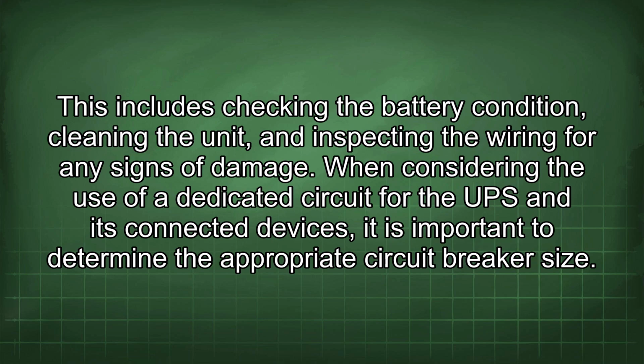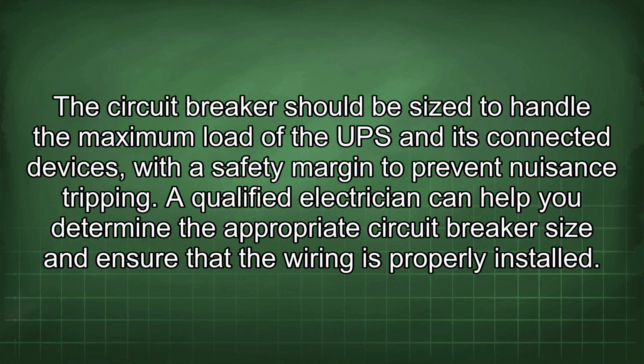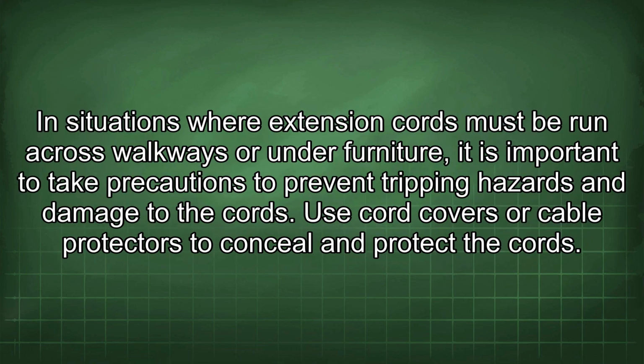When considering the use of a dedicated circuit for the UPS and its connected devices, it is important to determine the appropriate circuit breaker size. The circuit breaker should be sized to handle the maximum load of the UPS and its connected devices, with a safety margin to prevent nuisance tripping. A qualified electrician can help you determine the appropriate circuit breaker size and ensure that the wiring is properly installed. In situations where extension cords must be run across walkways or under furniture, it is important to take precautions to prevent tripping hazards and damage to the cords.